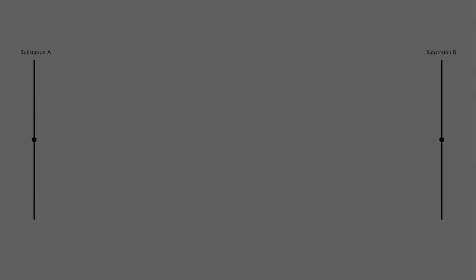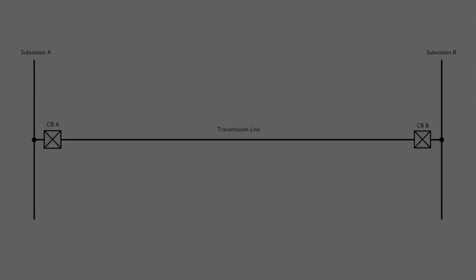This is the bus of substation A. On the right hand side of the screen, this is the bus of substation B. A transmission line, as shown, connects the bus of substation A and substation B. The circuit breakers of substation A and substation B are shown here as CBA and CBB respectively. Now we add current transformers in the diagram. CTA is the current transformer at substation A and CTB is the current transformer at substation B. Both of the current transformers are connected after the circuit breakers, as shown. This means both the current transformers are line side current transformers.